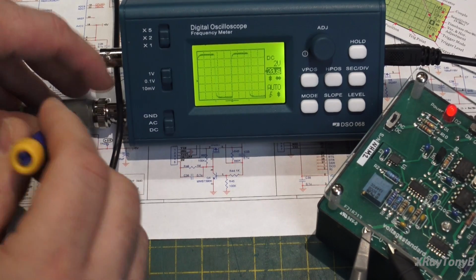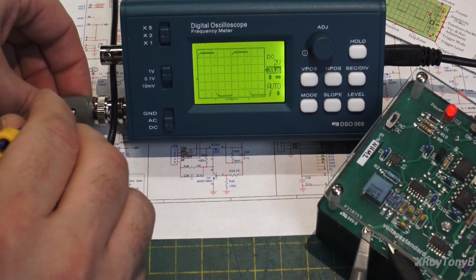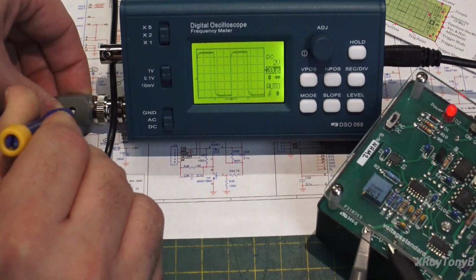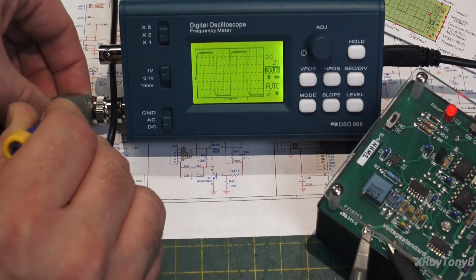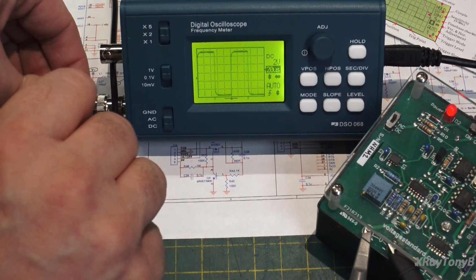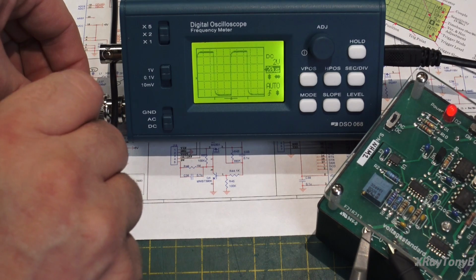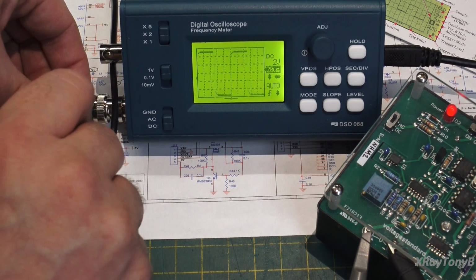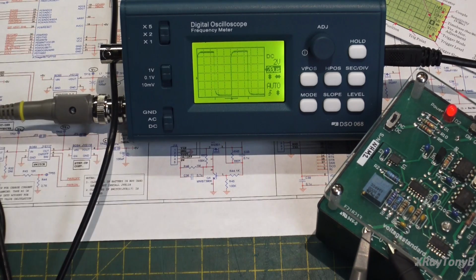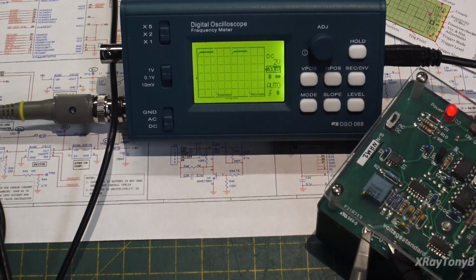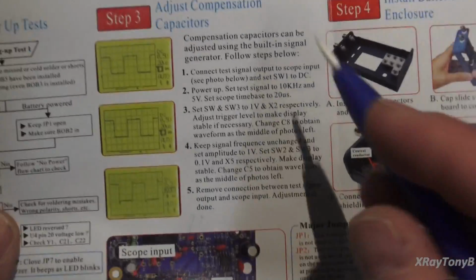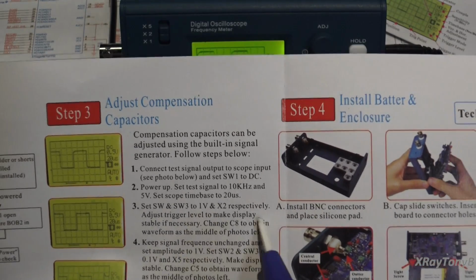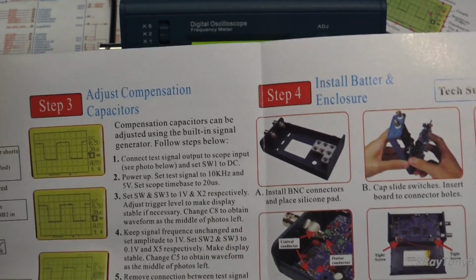Okay, I have a little non-metallic adjuster, and I'm going to adjust this to see. It's not really making much difference, is it? So what that might be is that this may be something internal to the scope itself that needs adjusted. And once again, there is a calibration procedure for that. Adjust the compensation capacitors. So let's do that. Let's take this apart and let's adjust this and see if we can get this all to read properly.